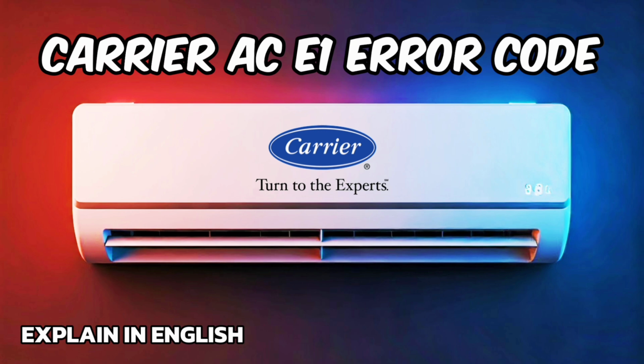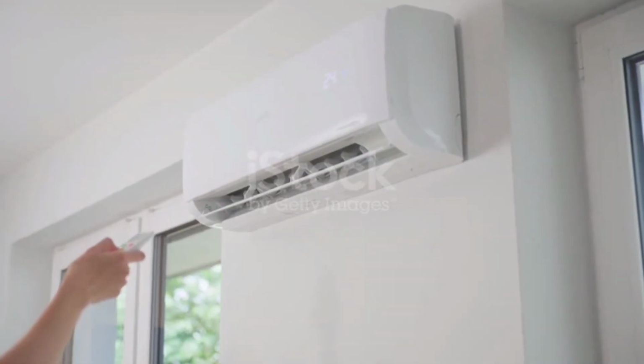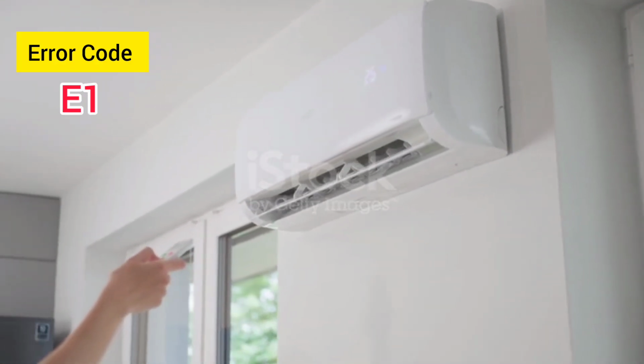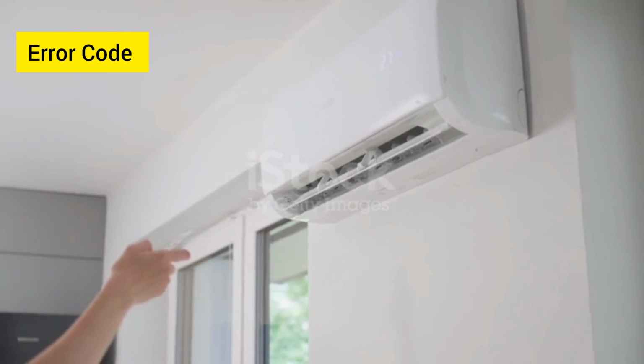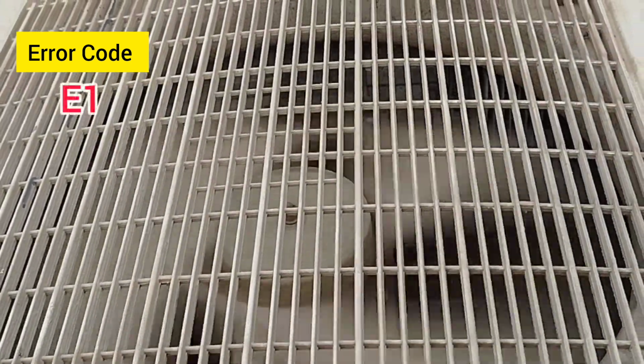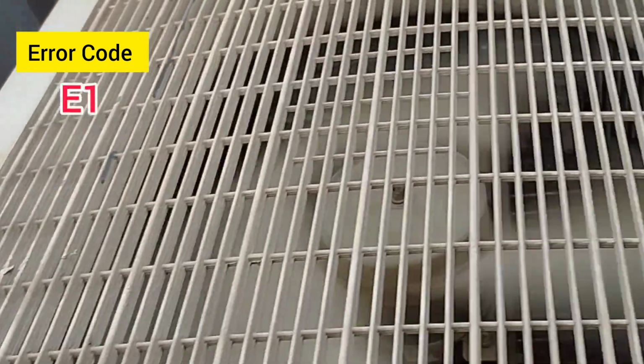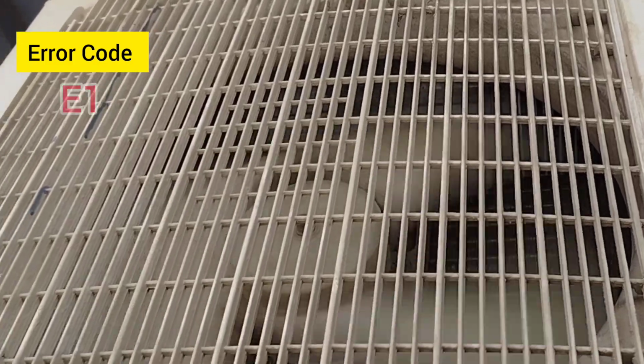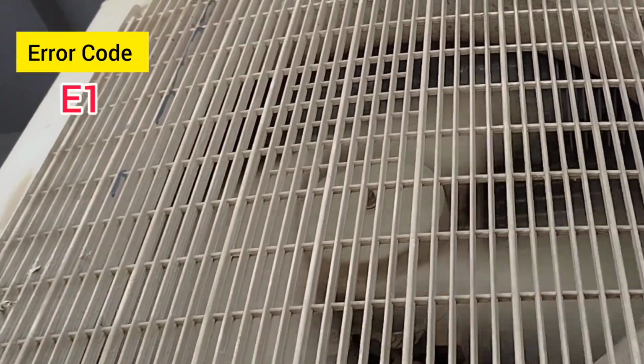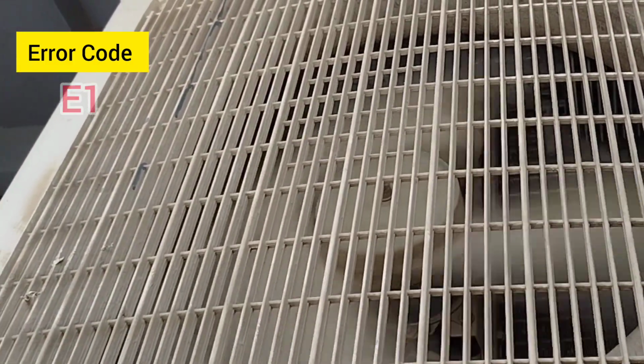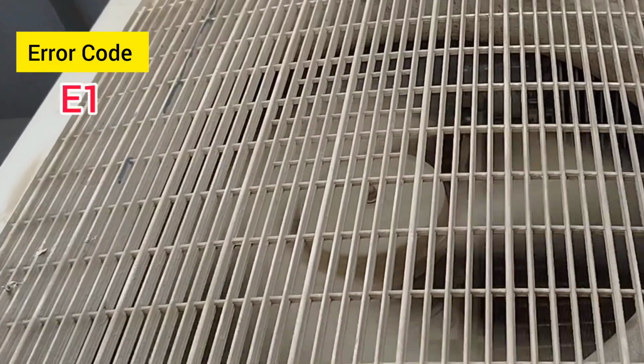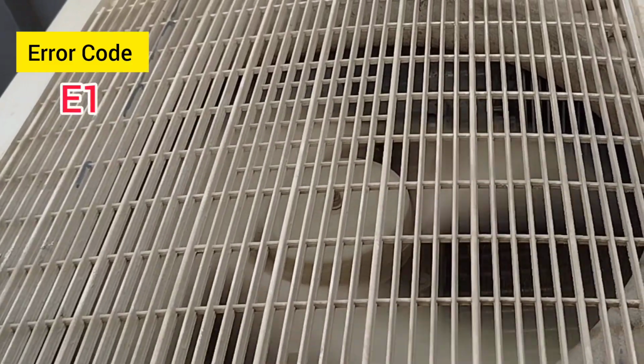A Carrier AC E1 error code indicates a communication problem between the indoor and outdoor units, often stemming from wiring issues or a faulty control board. Here's a breakdown of the issues and potential solutions. What the E1 error means.